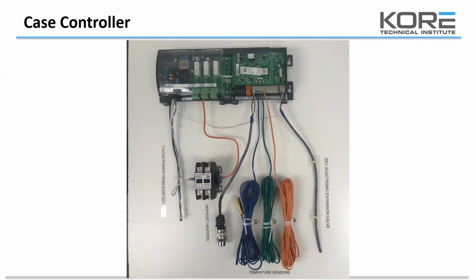In the case of the beer cave and the freezer, you'll see that there will be an additional defrost heater contactor installed to run the heaters in each of the coils. That's due to the amount of amperage that needs to go through the relay itself, and the case controller won't handle that type of amperage. We also can control the fans through that. You'll see the green plug to the left of the orange wire that we'll be able to turn the fans on and off.